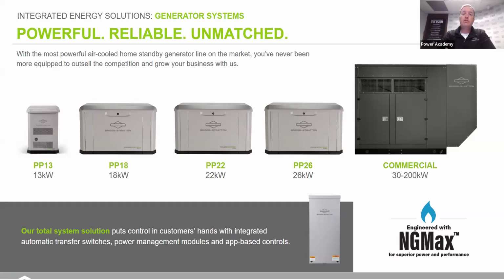The 26K, the 22, and the 18 also have what's known as NG Max. I didn't always realize this, and a lot of people probably don't, but when we tell you it's a 26 or 22K generator, that's on propane. If you run one of these generators on natural gas, they normally derate. But here at Briggs & Stratton we've optimized the generator's performance—ignition timing, exhaust manifold, intake manifold—so that whether you run it on natural gas or propane, you're still going to get the nameplate rating you see there.